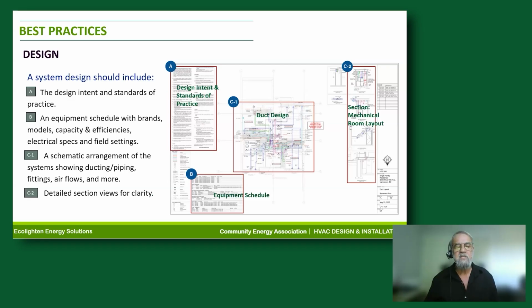A schematic arrangement of the system showing ducting, piping, fitting, airflows, and more. Where's everything going? What size is it? How's it getting around that beam? How's it going to terminate? Is it going to be a nice discrete reveal above a cabinet, or is it just a standard off-the-shelf grill? Every little detail should be in the design layout, including airflows and everything else, so that you can measure eventually the performance of the installed system against the intended performance from the design system.